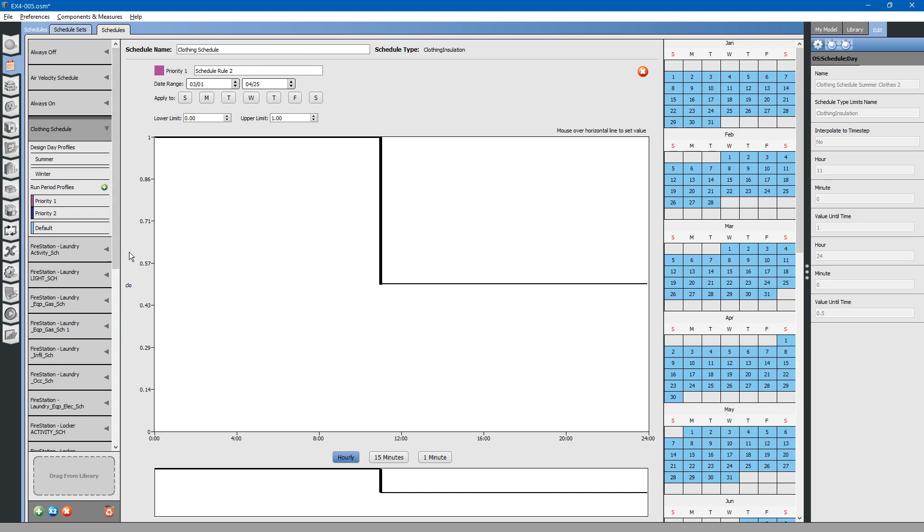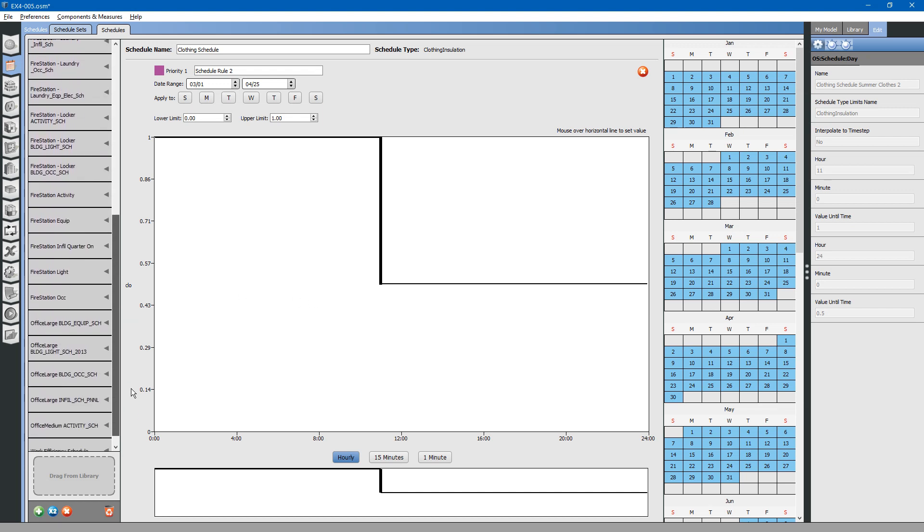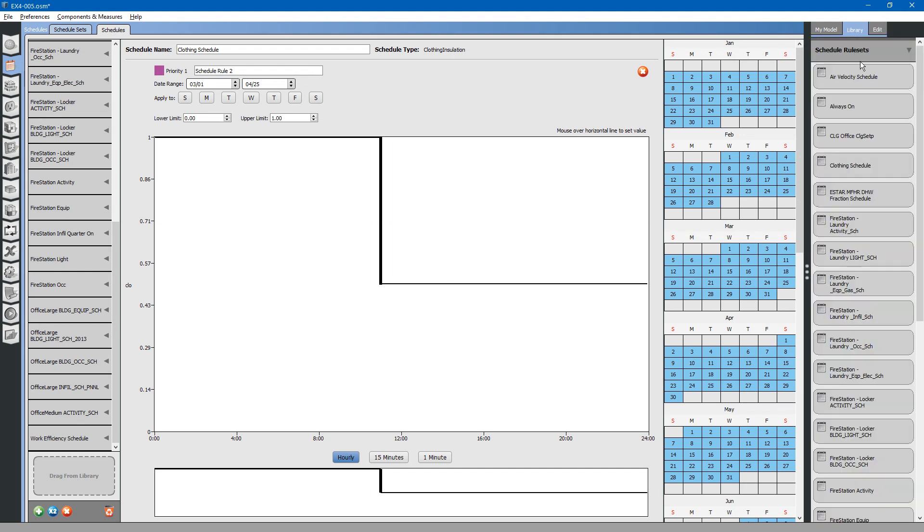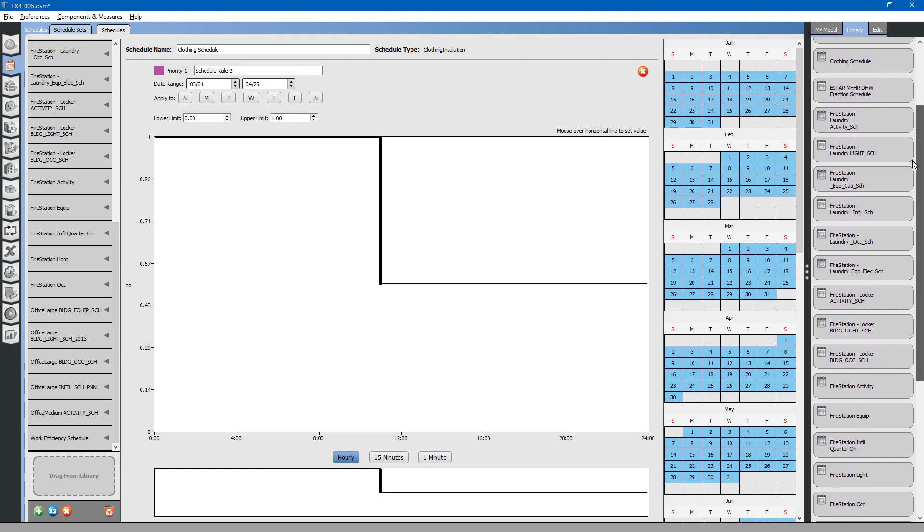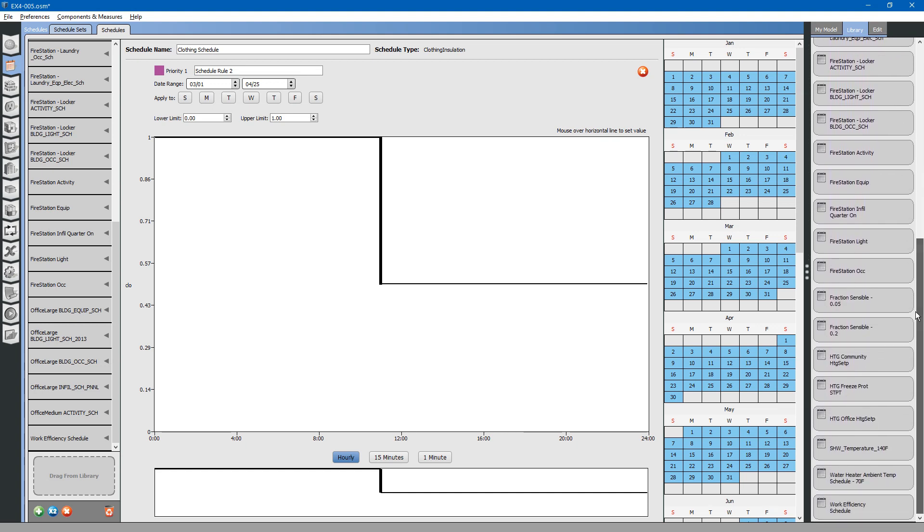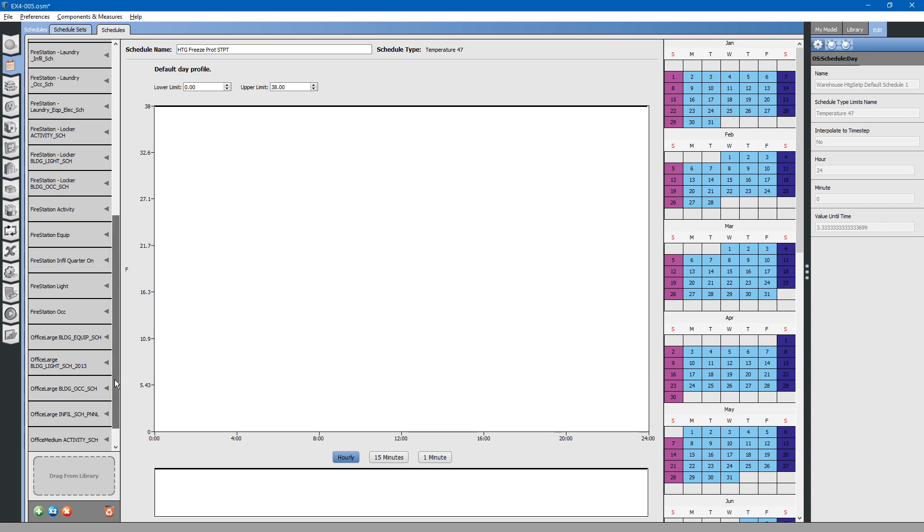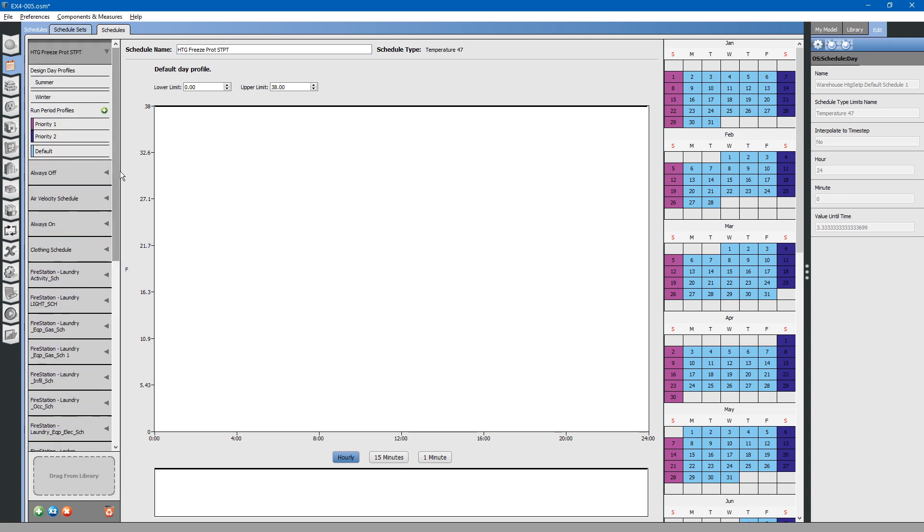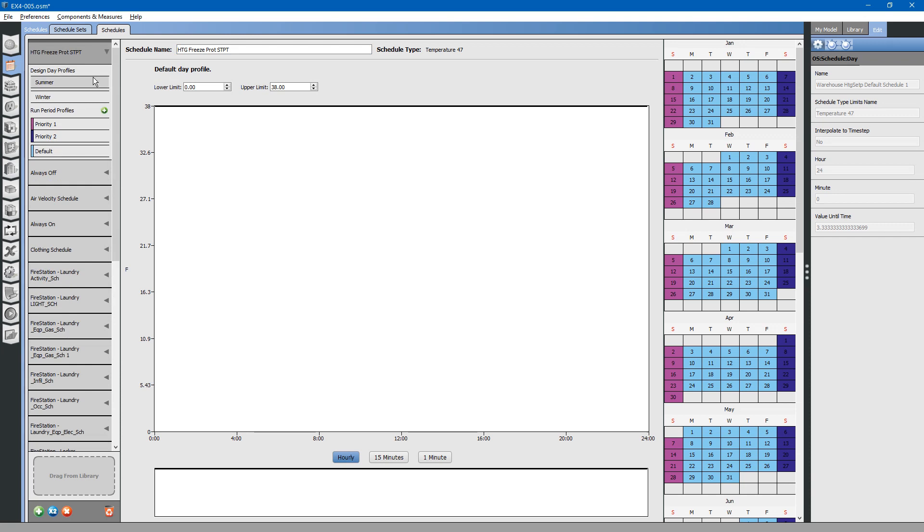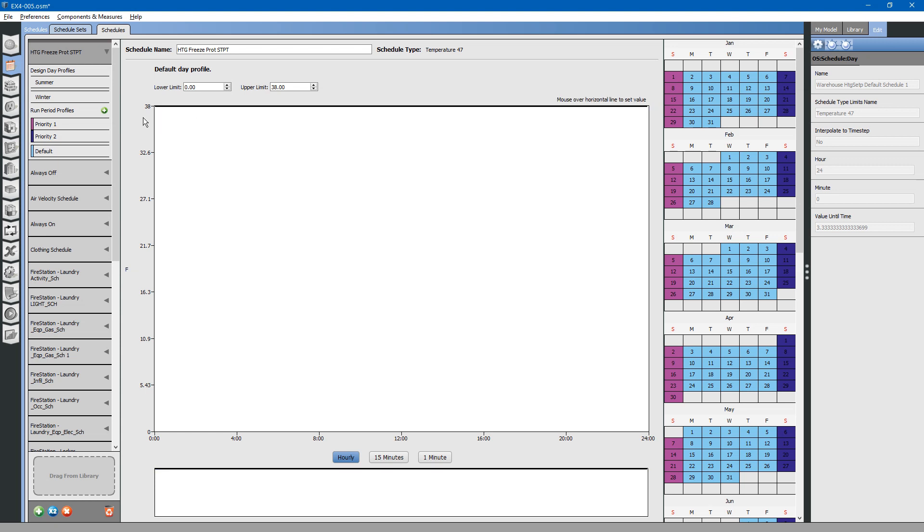Let us create a schedule for a thermostat set point. You can simply go to the library as we imported our library before. Let us look for a thermostat schedule. For the apparatus bay, the temperature will be held constant throughout the year at a freeze protection set point. You can drag this schedule into the schedules library and drop it here. You will notice that it was dropped into our schedules set. The default value is to maintain the space at 38 degrees, basically above freezing.